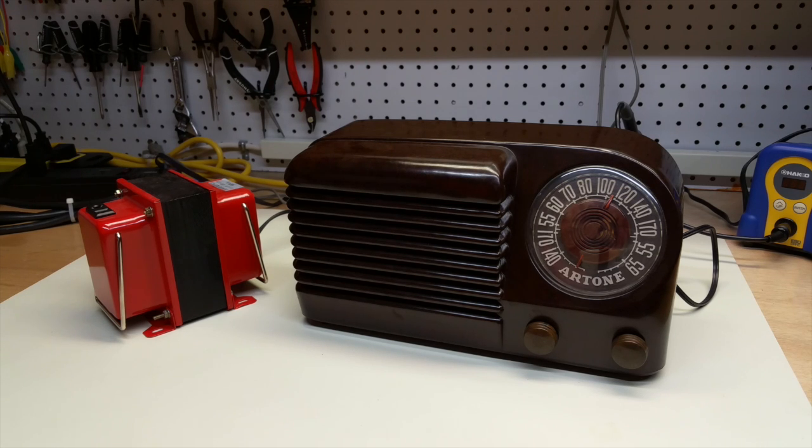One final point. Not all isolation transformers provide isolation as we've talked about in this video. Some units are sold and designed to isolate or suppress electrical noise on the power line. And in doing so, they carry through the ground reference to the secondary side of the transformer. Such a transformer will not protect you unless it's modified.